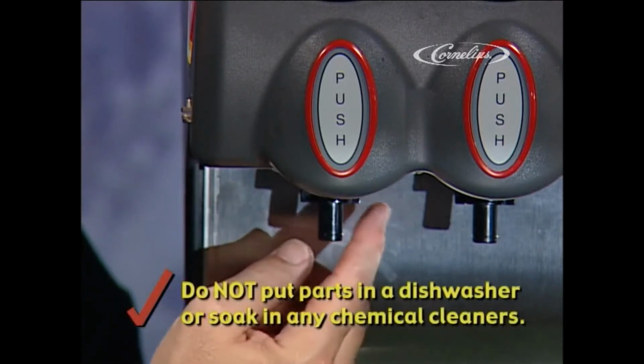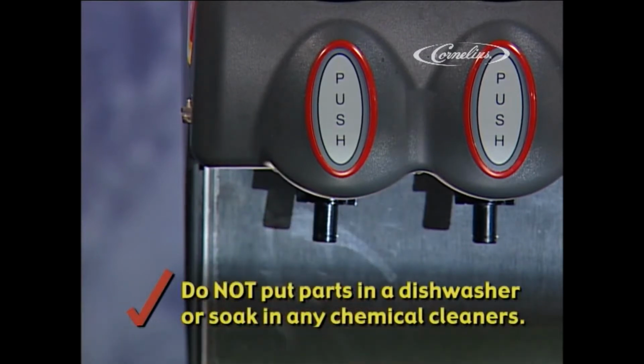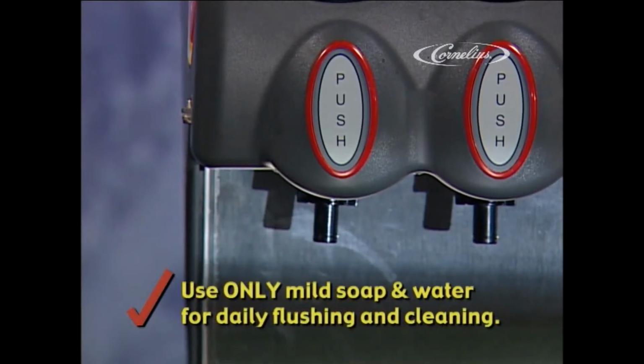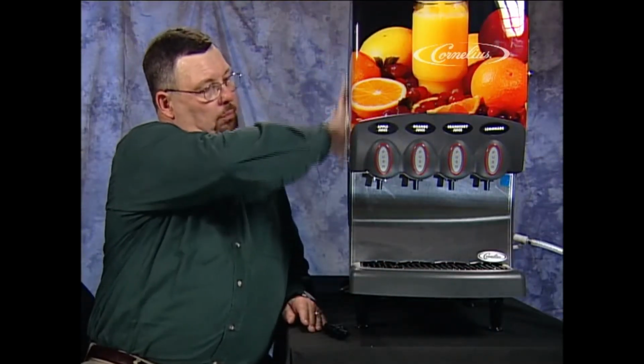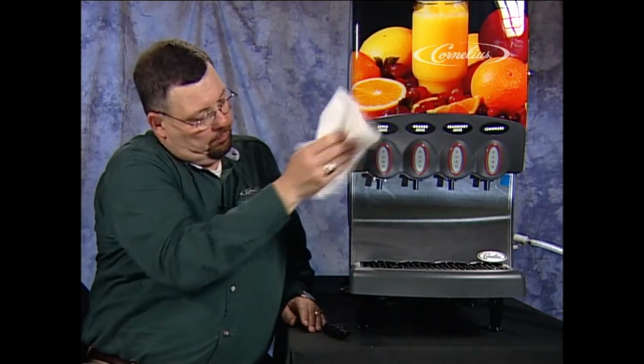Do not put these parts in a dishwasher or soak them in any kind of chemical cleaner. Only mild soap and water should be used for the daily flushing or for the daily cleaning. It's also a good idea to use a clean damp cloth to wipe down the external cabinet and the splash areas periodically.